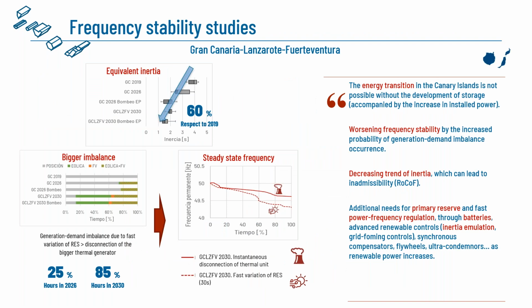Regarding frequency stability studies in the Canary Islands, we can see that the foreseen increase of renewable capacity in these isolated systems means a great decrease of system inertia, as we explained for the Balearic Islands as well. Power electronics coming from renewable energy sources displace synchronous generators, and thus the inertia of the system decreases, as expected.